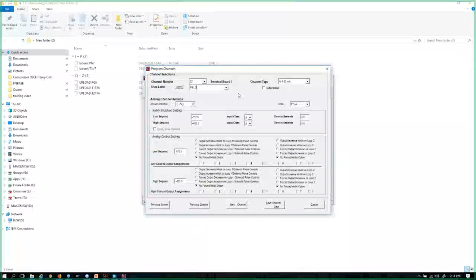Sometimes a lot of people want not to measure the suction pressure right at the skid, but they want to measure what the field pressure is. Maybe there's some suction control valves or block valves between this measurement point and the actual scrubber on the first stage suction of the compressor package. Well, one thing to know off the bat is when you select a new pressure range or set up a channel, PSIA, absolute pressure, will come up as your default. So just be sure that you change that before you're done here.